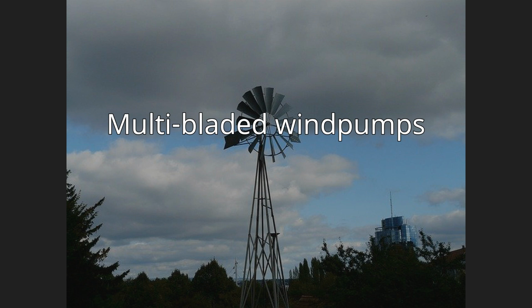Wind pumps require little maintenance, usually only a change of gearbox oil annually. An estimated 60,000 wind pumps are still in use in the United States. They are particularly attractive for use at remote sites where electric power is not available and maintenance is difficult to provide. A common multi-bladed wind pump usefully pumps with about 4 to 8% of the annual wind power passing through the area it sweeps. This lower conversion is due to poor load matching between wind rotors and fixed-stroke piston pumps.